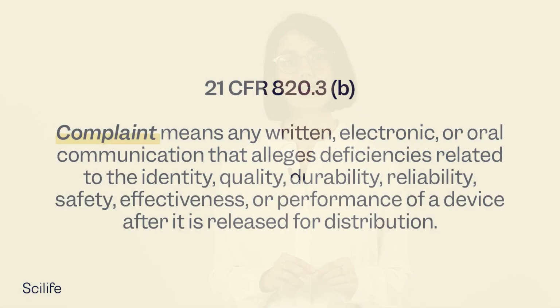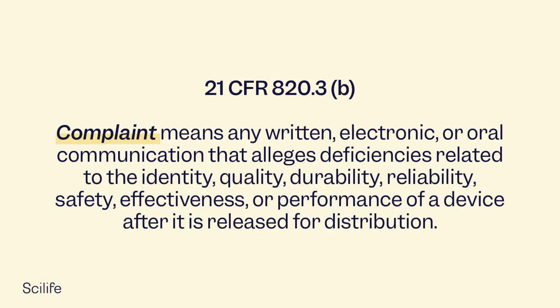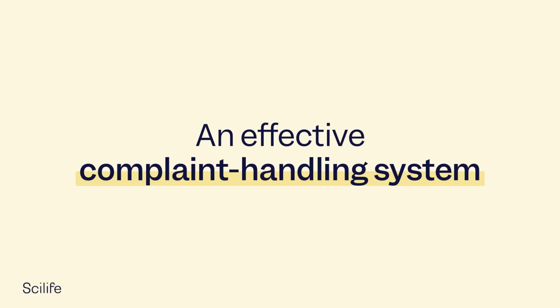However, according to 21 CFR 820.3b, the regulation used in manufacturing medical devices, a complaint is any written, electronic, or oral communication that alleges deficiencies related to the identity, quality, durability, reliability, safety, effectiveness, or performance of a device after it is released for distribution. Now let's move on to the complaint handling process.